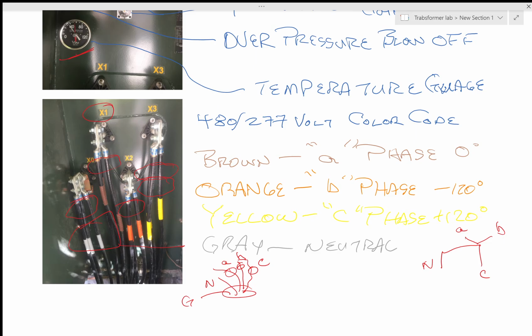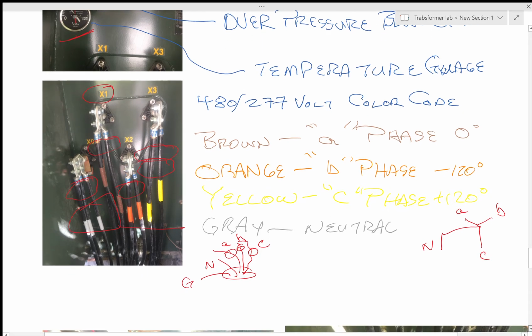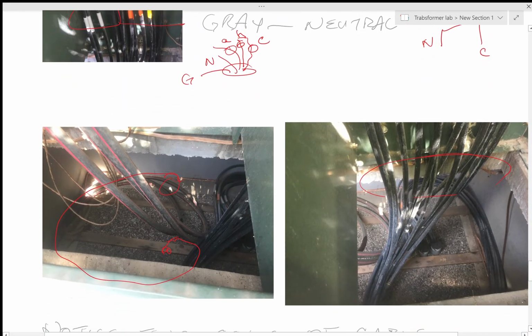Now you can derate and run more than one ABC phase in a conduit. So you could run 2 or 3 sets of ABC phases in a conduit. But when you do that, you have to derate the wire, which also presents problems. So if you go back down here to the ground, well, I guess you can. Maybe you could barely see it though.